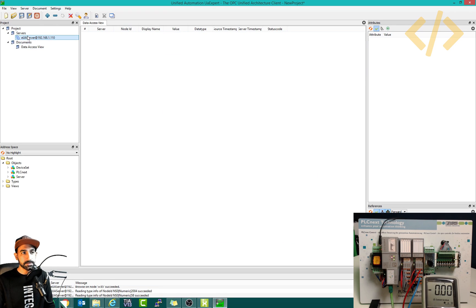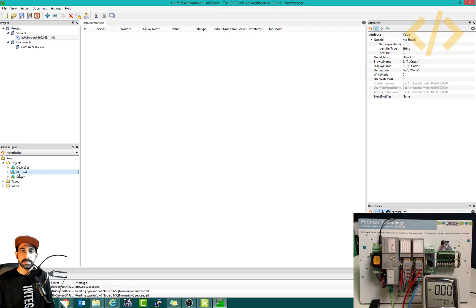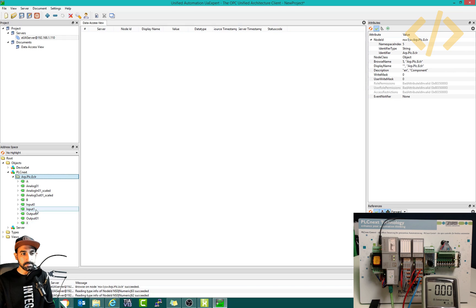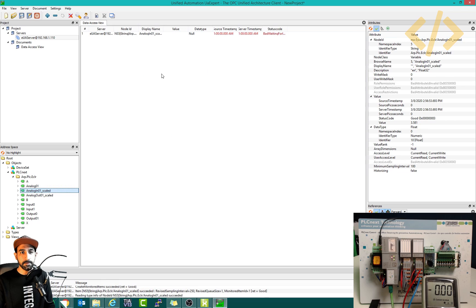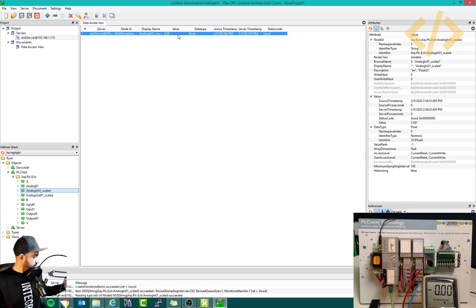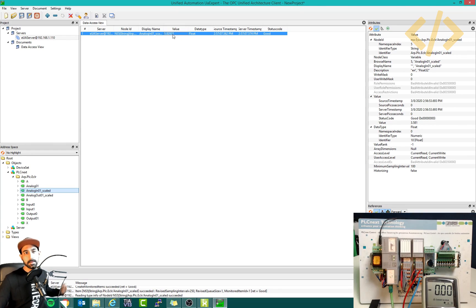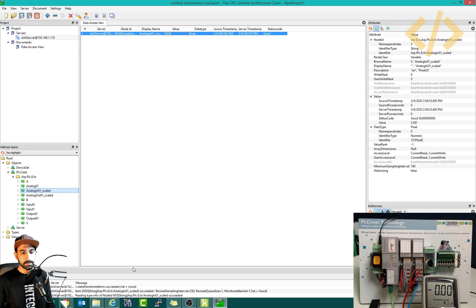Once you continue, you can see PLC Next listed here. Inside PLC Next there is a folder called ARP PLC. If you open it, you will see all your tags. Let's take analog scaled — I'll add it here. You can see the value is 3.58, coming from analog input channel one. If I change it from my trainer, you can see it's increasing, and that's the same value we have in our HMI.